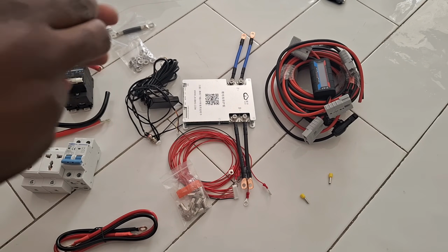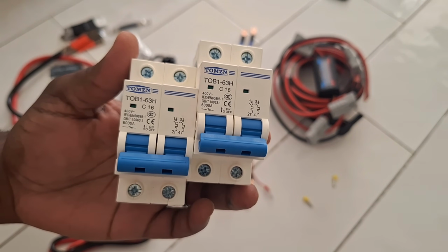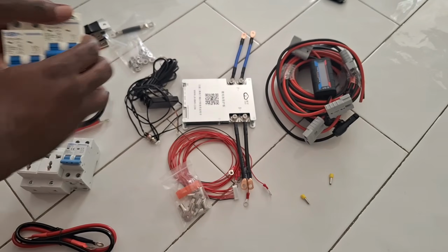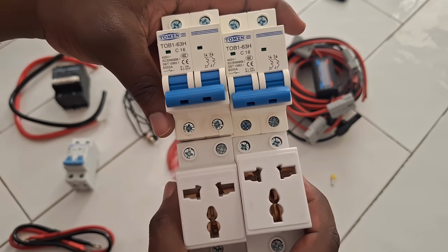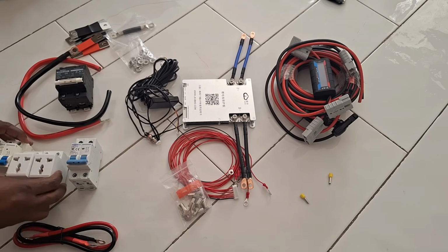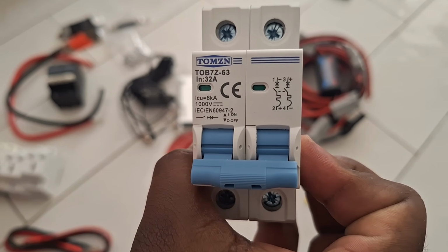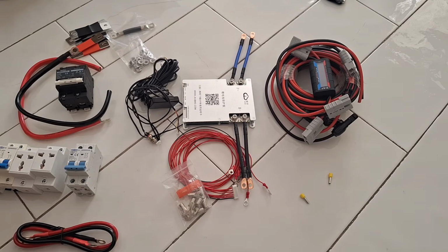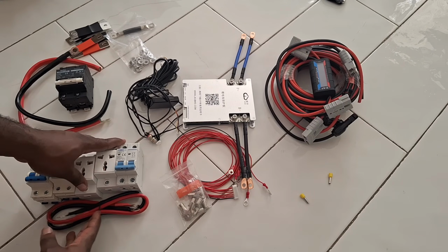So these are the circuit breakers that I'll be using for the output of the inverter. They are rated at 16 amps each. And here you also have some DIN rail power outlet modules that I can use to plug in extension cables or appliances. This is a circuit breaker that I'll be using for the grid input, rated at 32 amps.